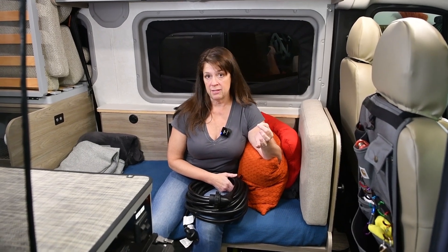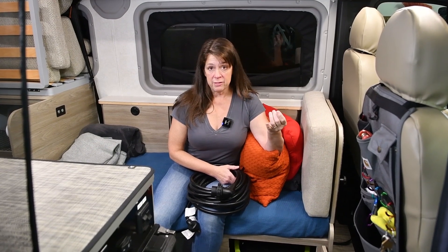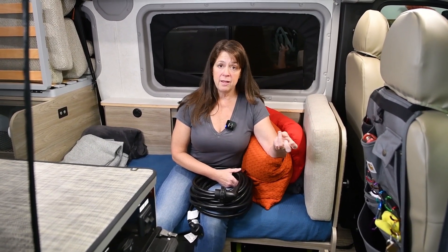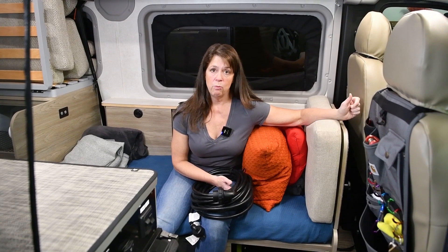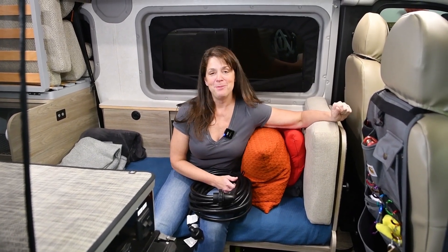So we have an electrical mystery. We've got three 120 outlets. One trips every time it's plugged into shore power - we cannot get it to stay live. The second one is never live; it's just always dead. And the third one is live when it shouldn't be, because all of the circuit breakers have been closed. We don't know what's going on. So you get to come with us as we debug this problem.